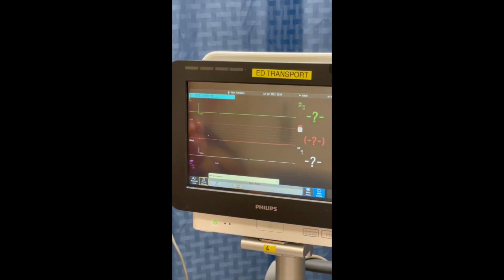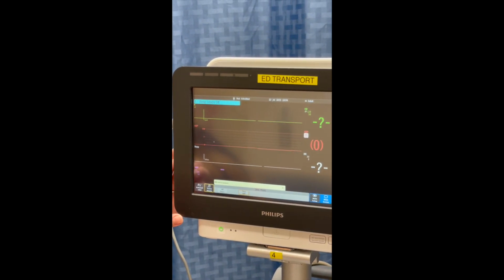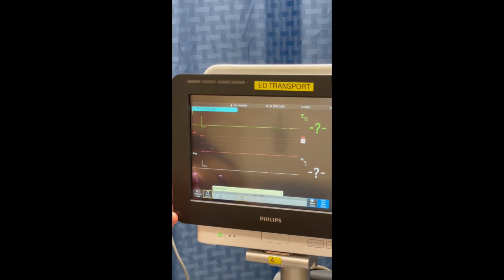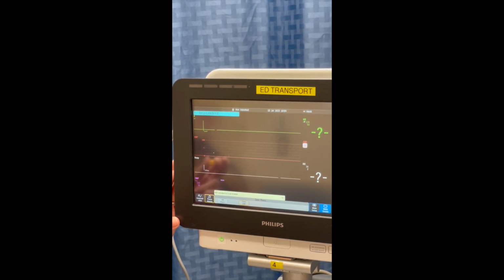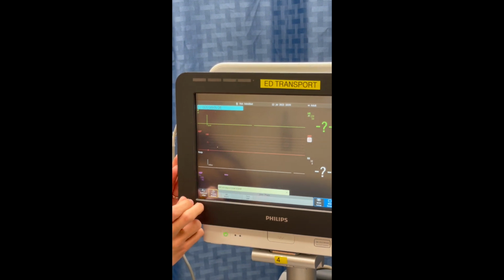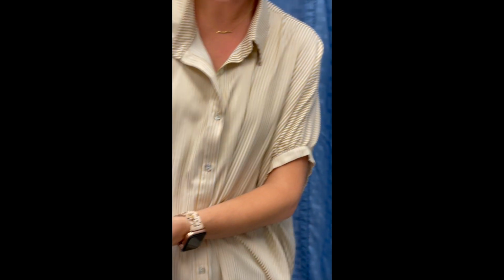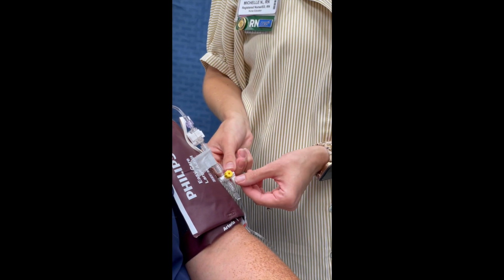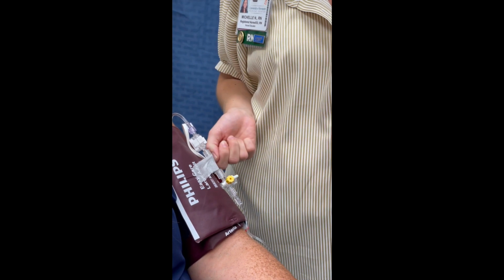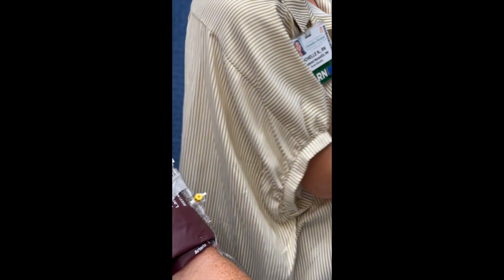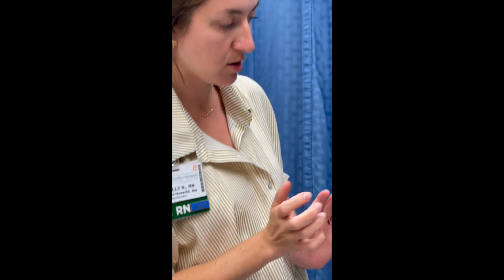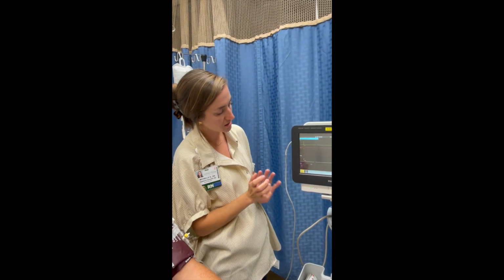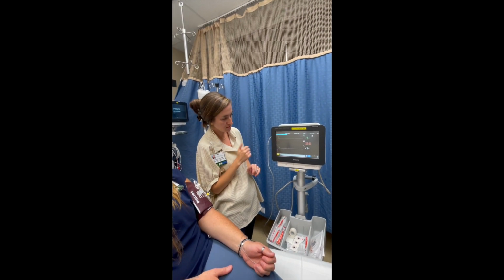You'll hear one beep and see a dialog box that says the 0 is in process. And then you will hear a second beep that will say 0 done with your timestamp. Replace your cap, return your stopcock to the neutral position, and identify your waveform, performing square wave test and comparing to previous blood pressure measurements.